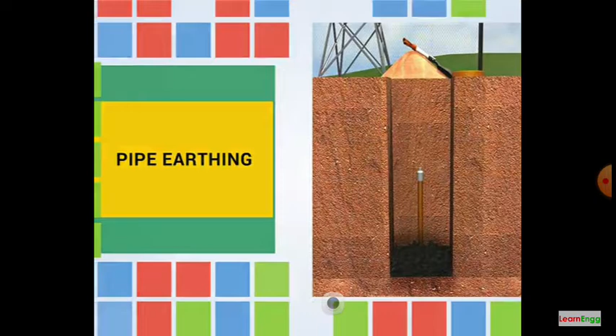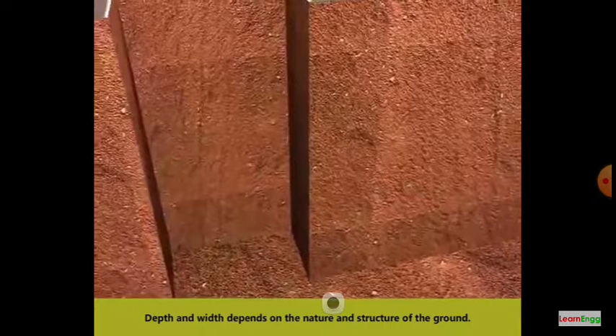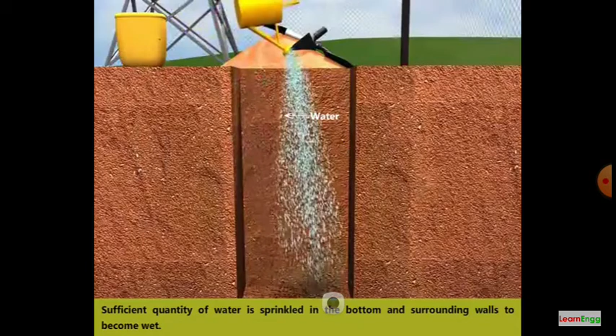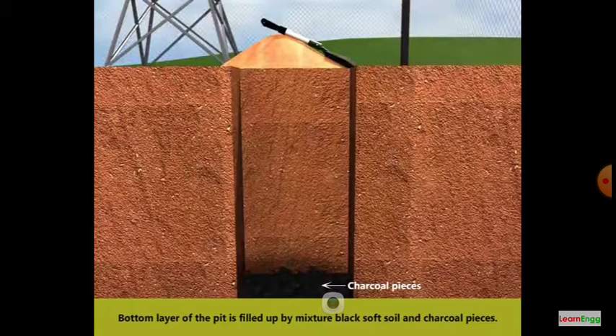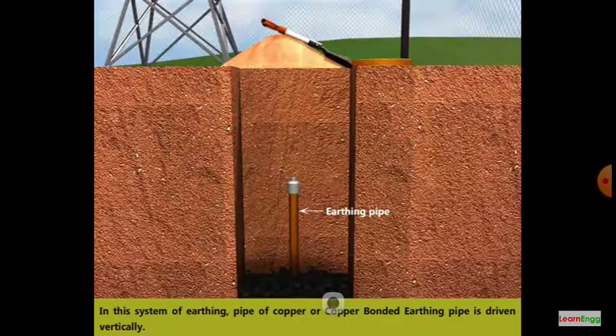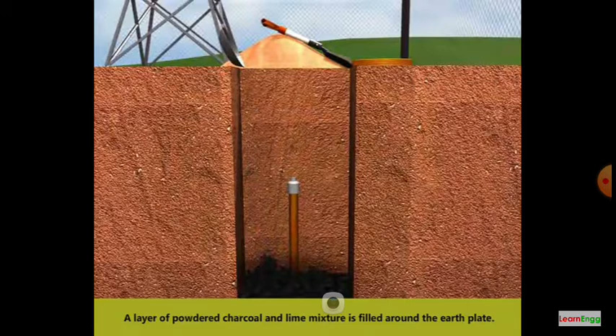Pipe earthing. This animated video describes a procedure for installing pipe earthing. A pit is dug about 20 to 30 feet in the ground. Depth and width depend on the nature and structure of the ground. Sufficient quantity of water is sprinkled in the bottom and surrounding walls to become wet. The bottom layer of the pit is filled up by a mixture of black soft soil and charcoal pieces. In this system of earthing, a pipe of copper or copper bonded earthing pipe is driven vertically. These pipes have rolled threads at each end. A layer of powdered charcoal and lime mixture is filled around the earth plate. A layer of salt is filled around the earth base. Rock salt generally.